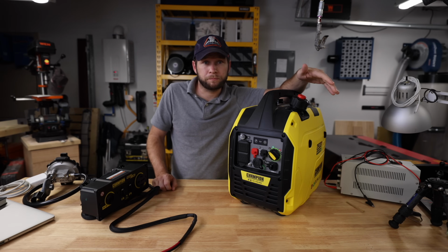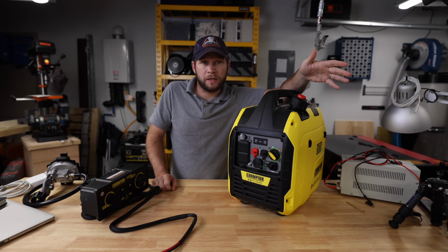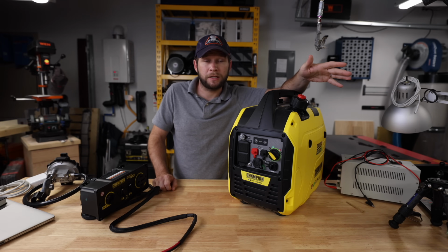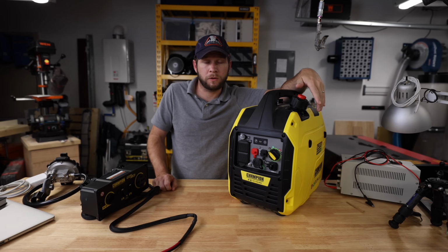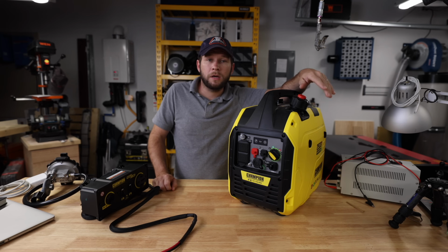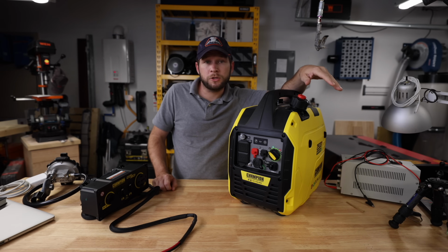This is the stator. Now, these are directly coupled. Essentially, the engine speed is the speed of the armature in the power head. This is what spins and is creating the power. So the RPM of the engine is the RPM of the generator. And this is what produces your power. Now, this is important because the speed of the engine in these is directly related to your power quality and your frequency of your power.